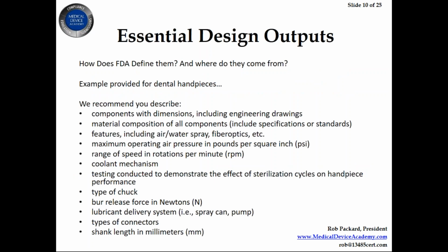The next question was interesting. It was worded as essential design outputs. How does the FDA define them, and where do they come from? There is no place anywhere that I'm aware of where essential design outputs is defined by the FDA. That specific wording I don't believe it is.